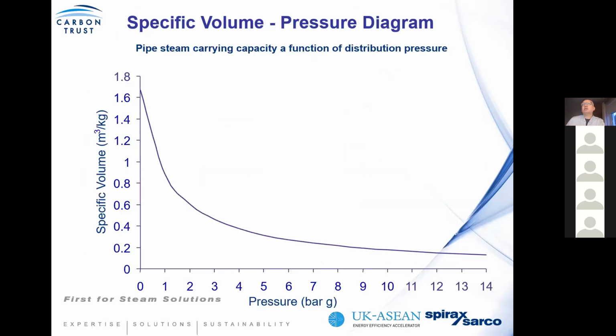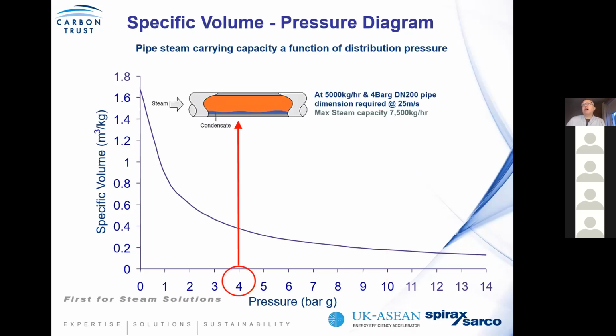Now, when we start talking about specific volume, the reason why it's important to understand why we generate steam at certain pressures and why we distribute at certain pressures is this. Let's take an example of a process that requires 5,000 kgs an hour. If we are to generate steam at 4 bar, you can see that according to sizing protocols, to ensure we don't have a velocity greater than 25 meters per second, you would need a DN200 pipe at 4 bar.